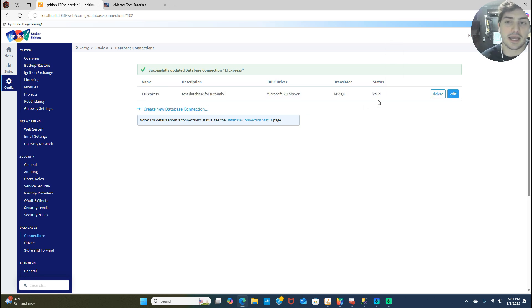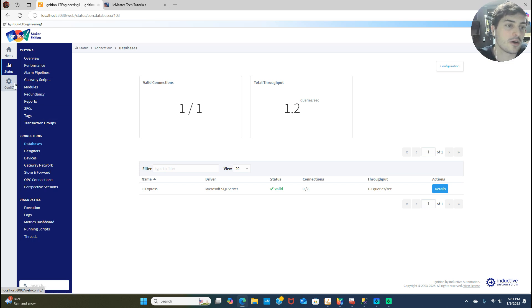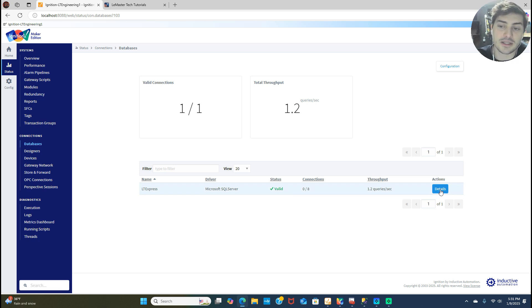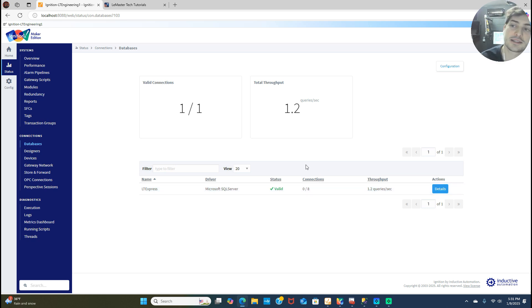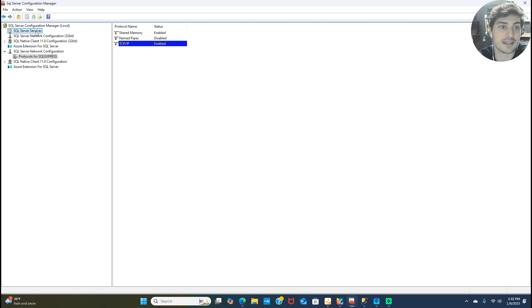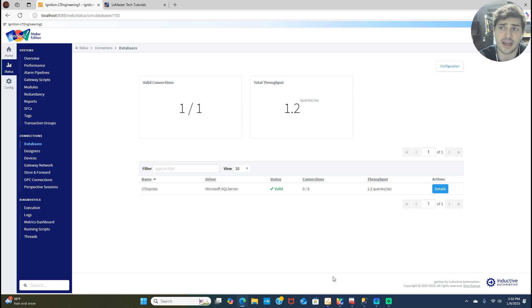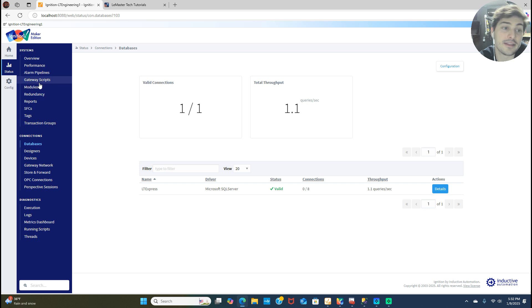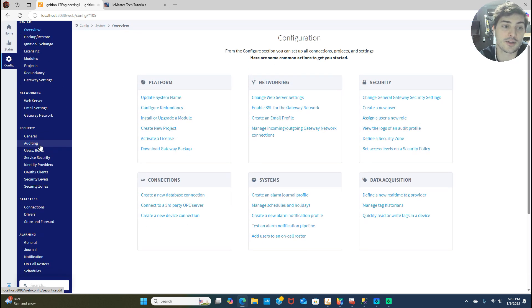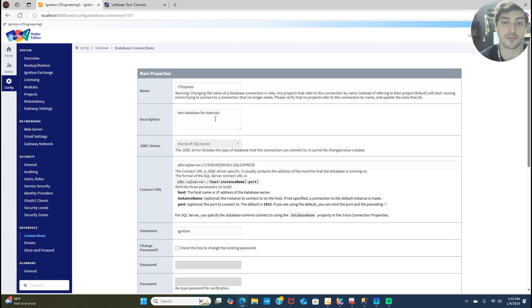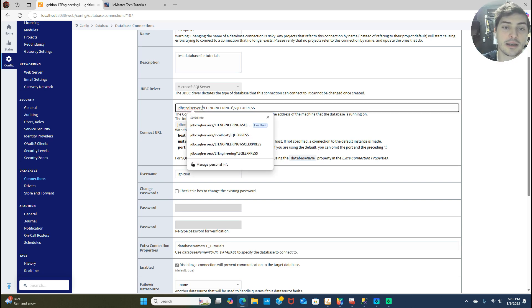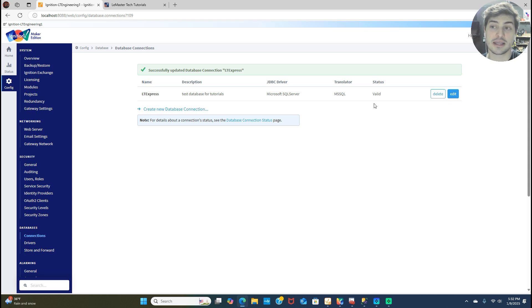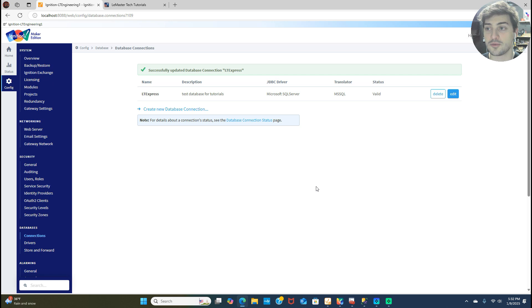So no longer in config over here on the left, you're in status, you go to databases. And if this is faulted, then this will be a little red exclamation mark icon and it'll say some of the details about why it's faulted. Some of the most common stuff is that your computer is actually getting blocked from accessing SQL because of a firewall restriction. Some of the other most common stuff is you actually don't have the SQL server browser running. You could definitely have an account where you typed in the credentials wrong, just like I did. And then another possibility is you got the host name or the database name wrong. So there's a lot of common errors that you could run into here. But the important thing hopefully that this page shows you is that there's not actually all that much going on. So most issues are likely in a tool or a network or firewall policy that you need to go fix outside of ignition.